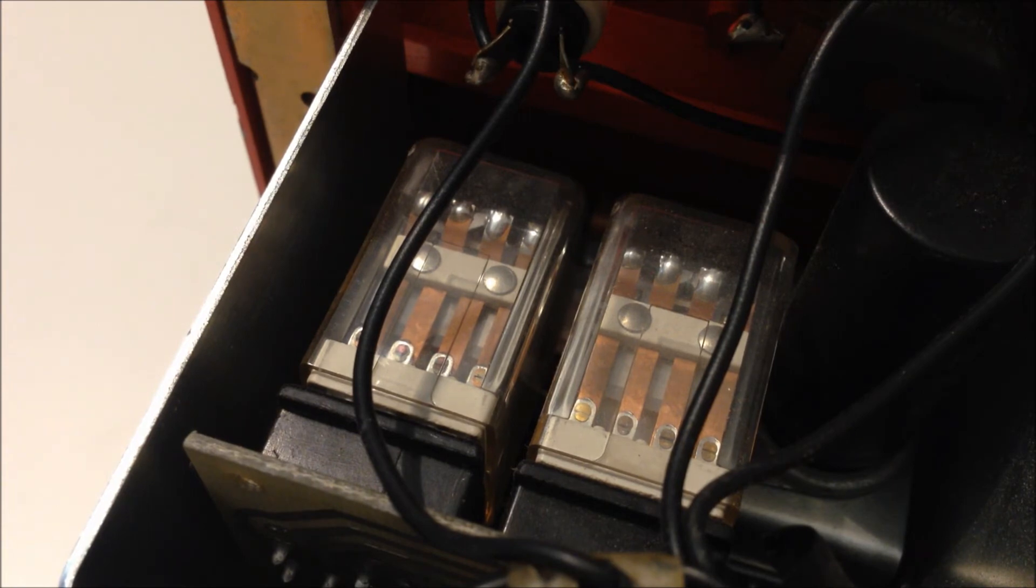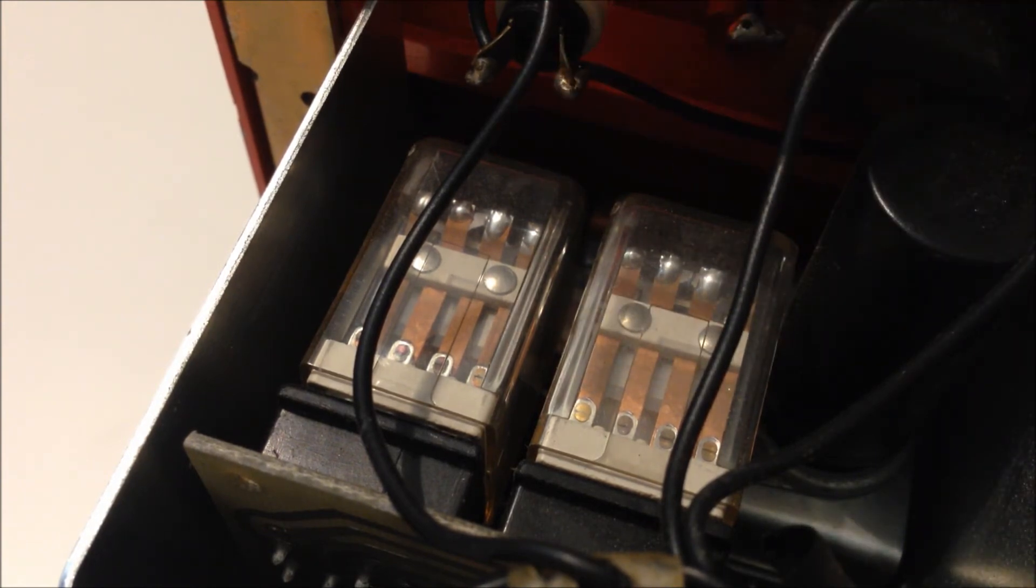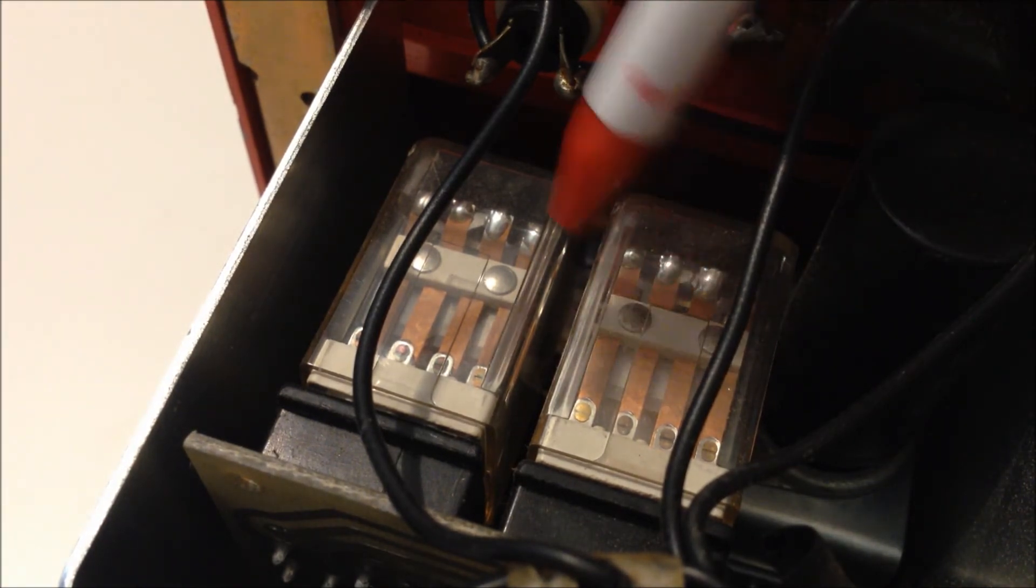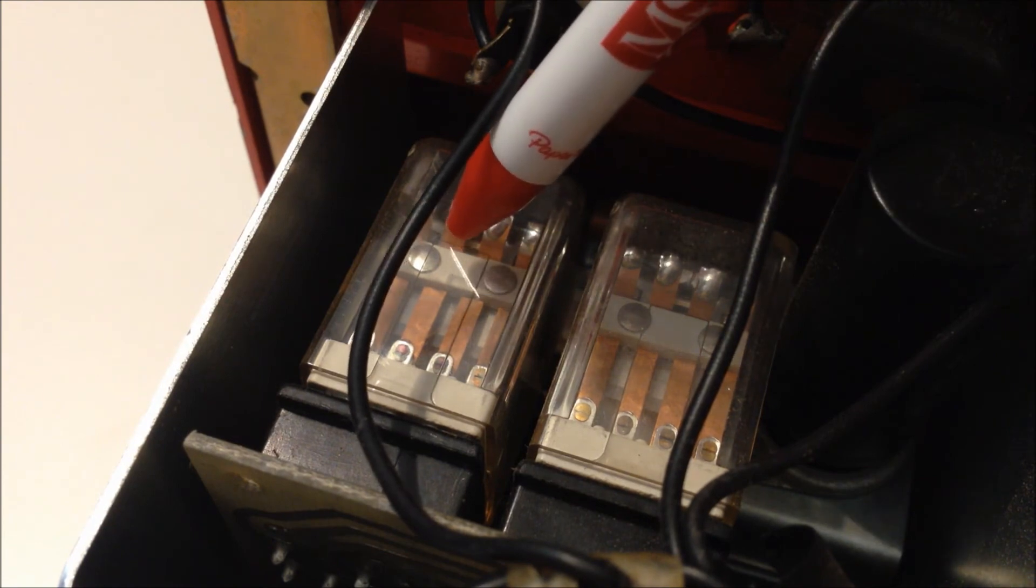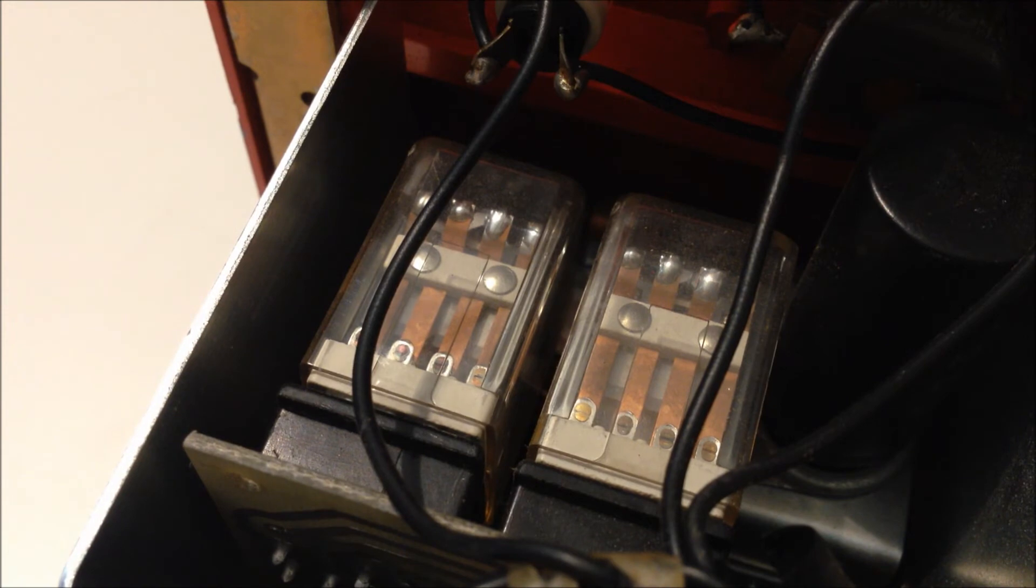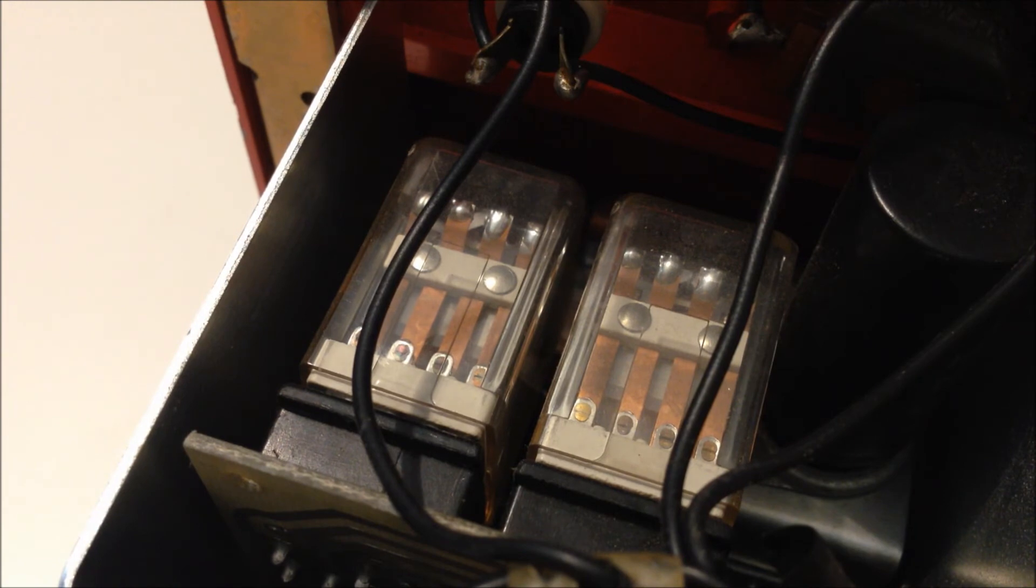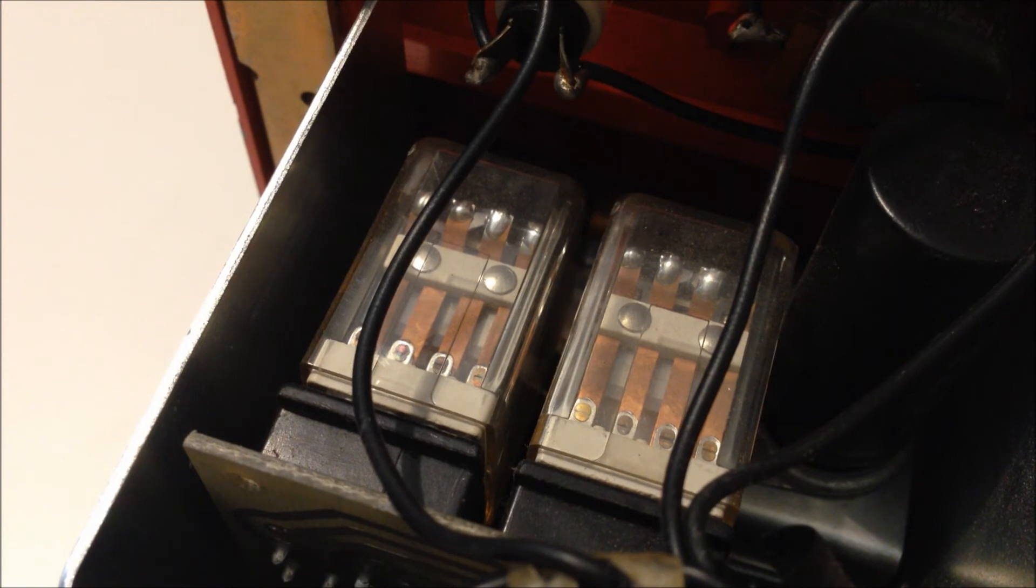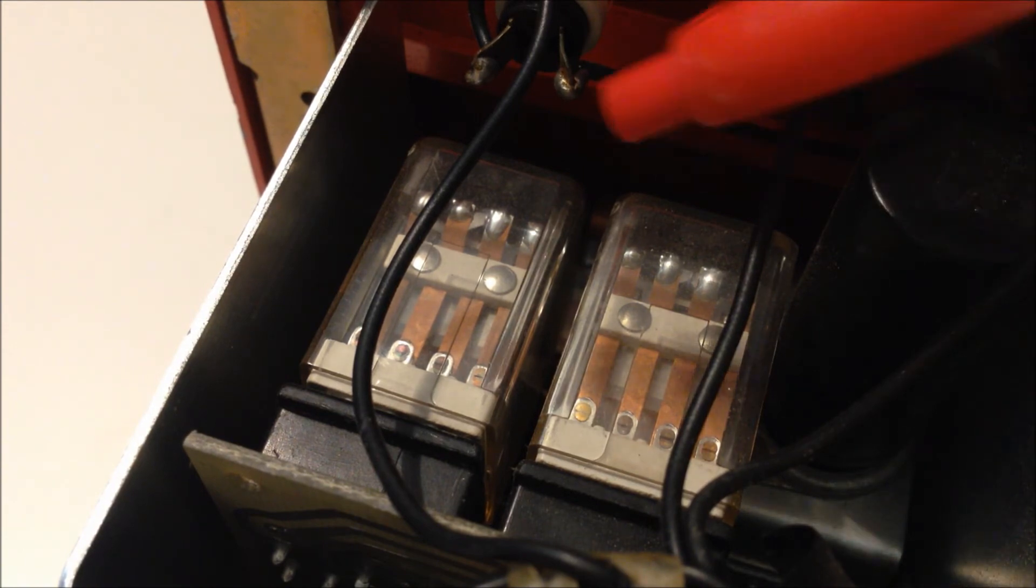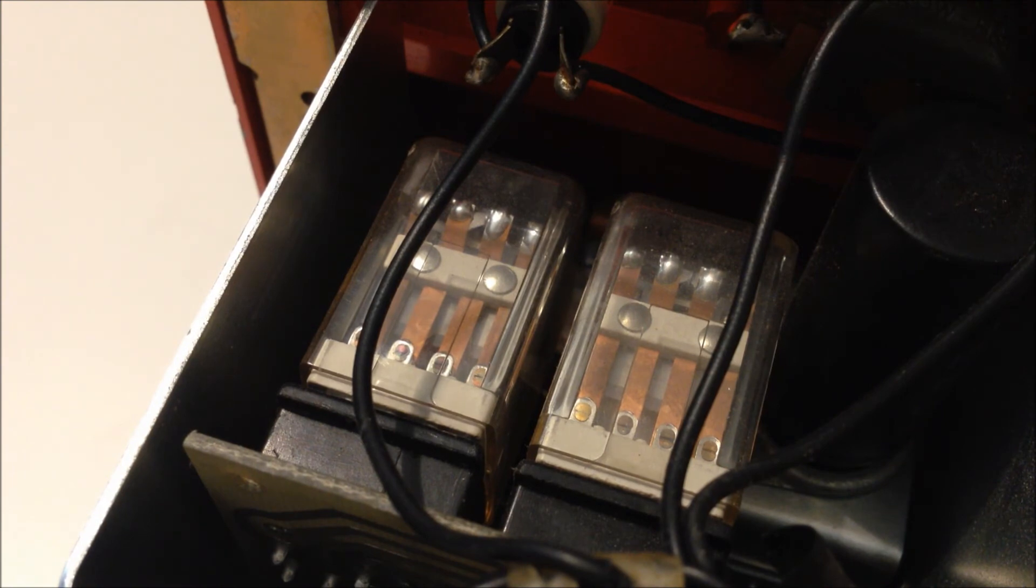So as you can hear, the unit is currently running its code and I honestly expected one of these two relays to be wired into the micro switch. However, it now appears that this relay is acting along with the reset switch. What this relay is acting as right now is the shunt which cuts off the power to the remainder of the circuit while the pull station is operating. What that does is it prevents multiple codes from being transferred to the horns from multiple pull stations. So the device that is electrically closest to the panel, when they're operating, if there's a scenario where multiple pull stations have been activated, that's the pull station that will take priority over the rest. Because this relay would have cut power to the remainder of the circuit.